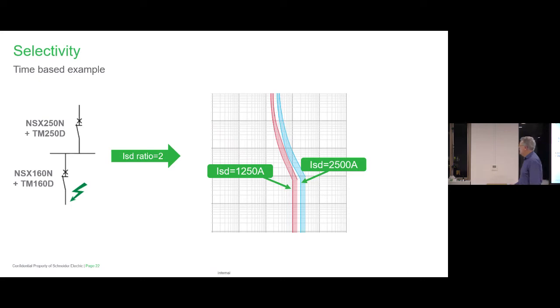And you say, well, where did you get those figures from? Well, because they're thermal magnetics, there is a fixed instantaneous value, is another way of saying it, but short delay time for those breakers. But when you go into electronics, they can be different figures. But for thermal magnetic, there is a fixed value of a current that it will trip out in, and that's 2 times. So we know it's okay.